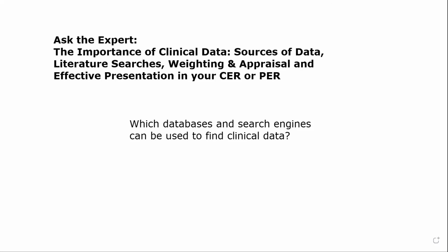So what databases and search engines can be used to find clinical data? It's easy to say first what you shouldn't be using. The internet is not acceptable. PubMed is not good, but it's better than nothing. But if you're searching PubMed on the internet, remember, there are only so many search criteria that can be used. It supports the AND and the OR and MeSH terminology and really nothing else. What the notified bodies are looking for is very rigorous medical librarian MeSH terminology and very good syntax in your search protocols.